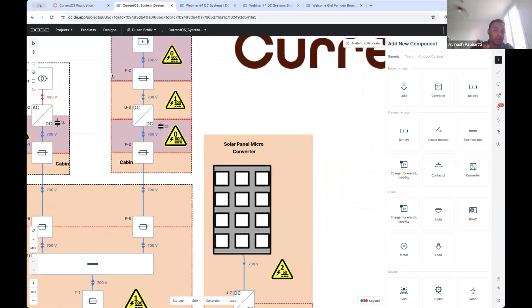When I protect a DC circuit with something classical like a fuse or breaker, which will save the property but still isn't sufficient for DC safety, then I come down to something called zone 1. In the area Dusan is focusing on, if there's a battery protected by a fuse, that's zone 0, and after the fuse it's zone 1. But just after the DC-DC converter, where the voltage changes, there's another exposed terminal.